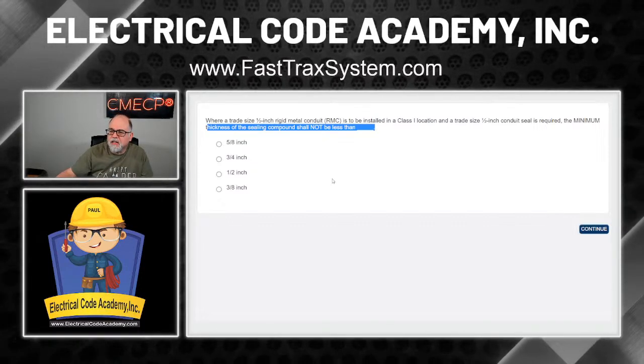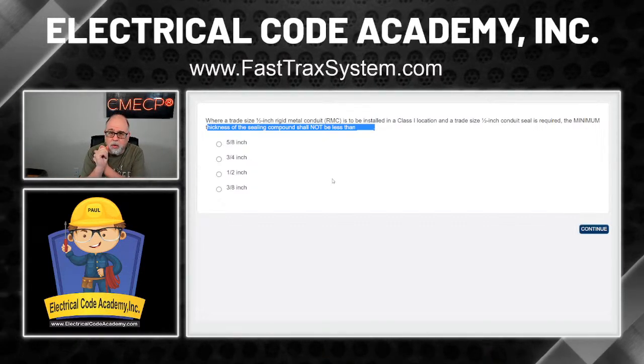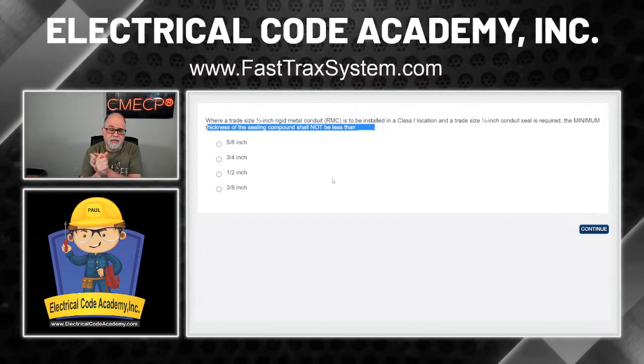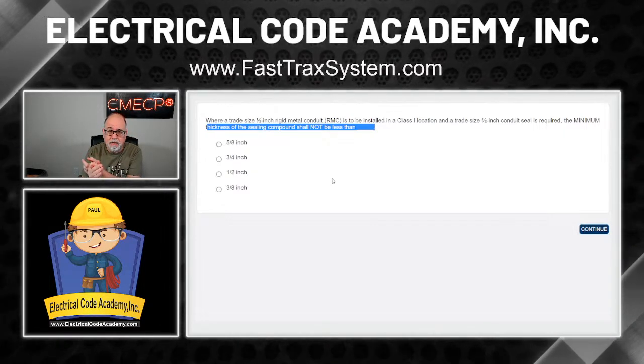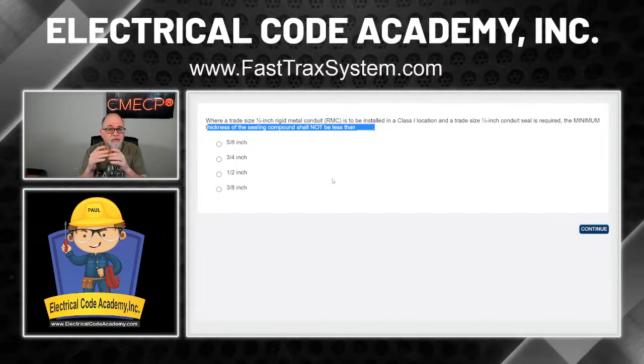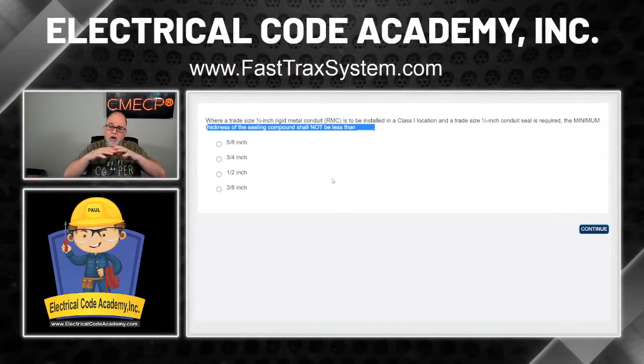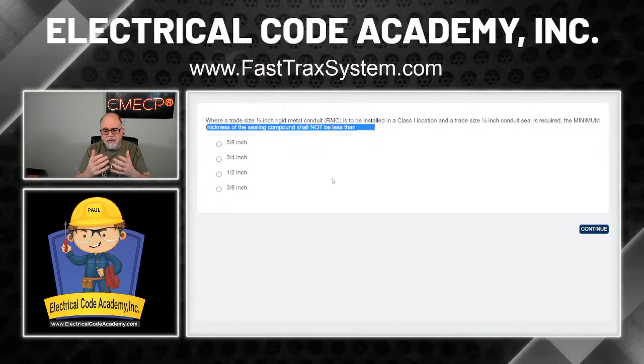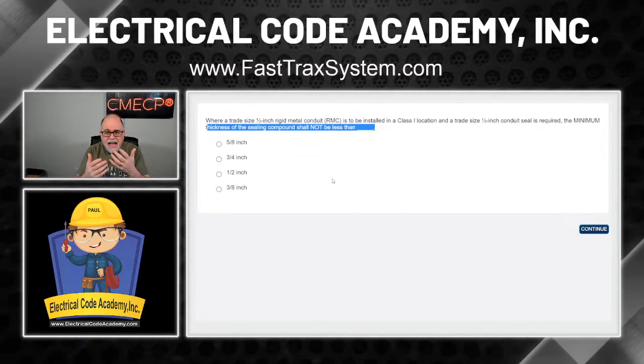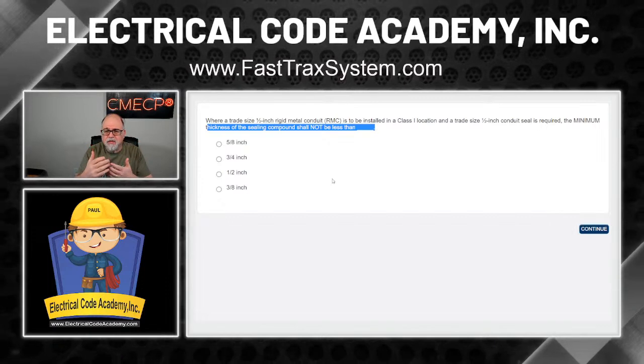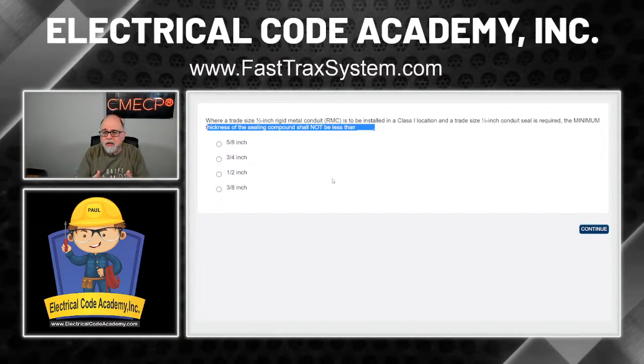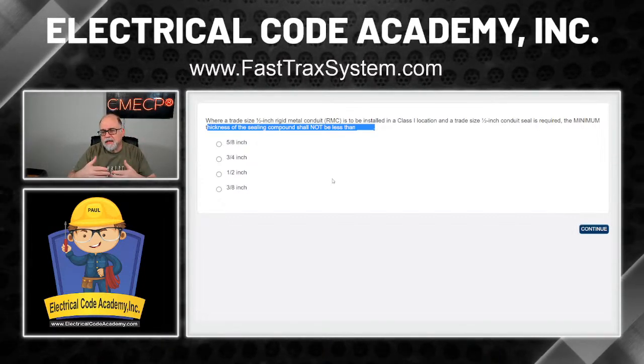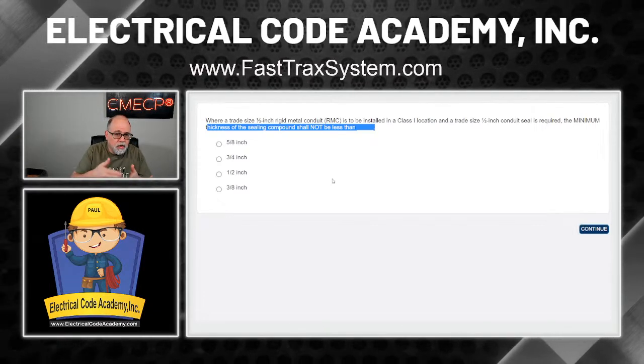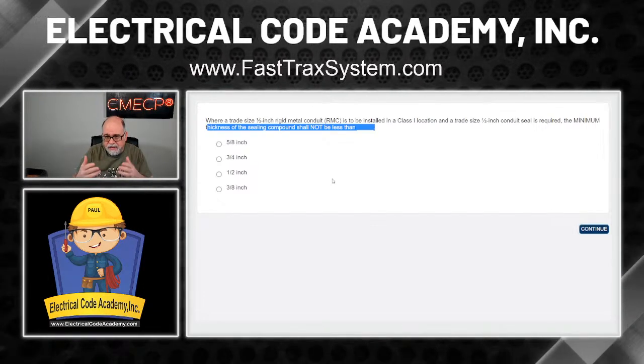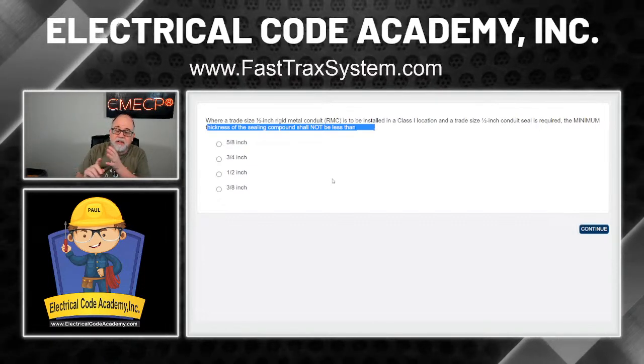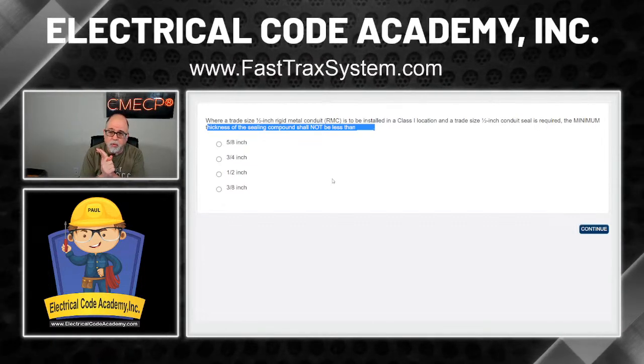So the first thing that triggers for me is it's Class 1. All right, so you need to know the article that deals with Class 1. That's Article 501. Hazardous locations start at 500. That's what gives you all of the things that constitute the different types of gases and their classification. It gives you some general rules. And then you start getting into Class 1, Class 2, Class 3, which is 501, 502, 503, that type of thing. So in our case, we know it's Class 1, so that's 501.